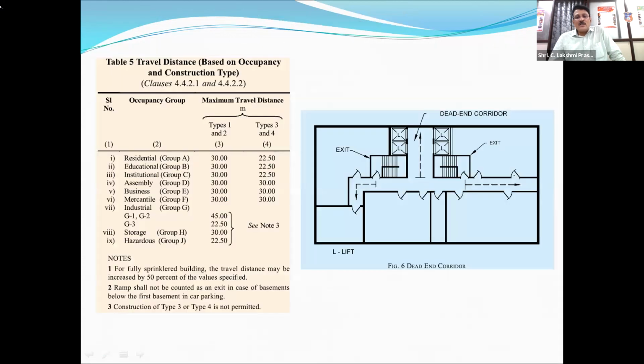Then dead end corridors. If you observe here, a dead end means that in case of emergency, if a person is traveling in the opposite direction of the staircase, then once he reaches the dead end, he has to return back to the staircase. That is the reason, where people are not familiar with the building design, dead ends are allowed only for a very short distance. For example, assembly buildings. Here the patterns are different every day, so people don't know the design of the building or the location of the staircases. So here only 6 meters is allowed.